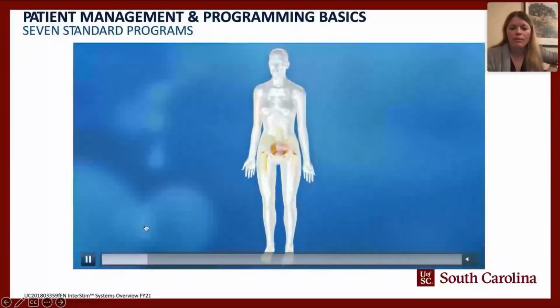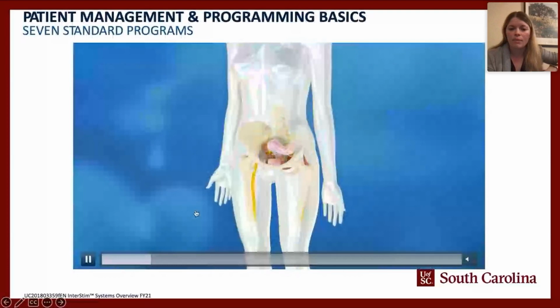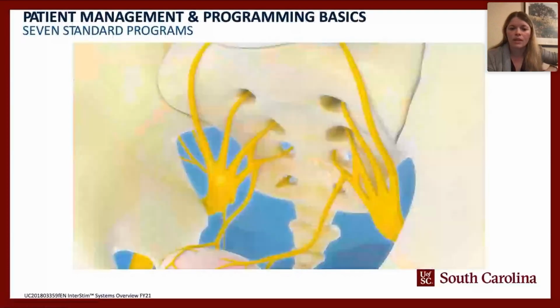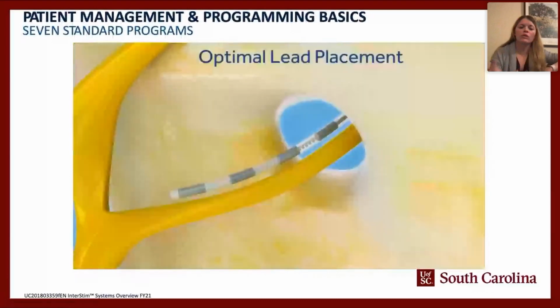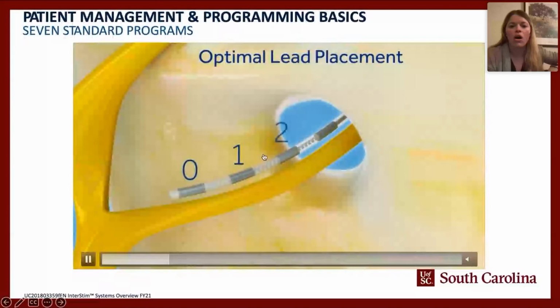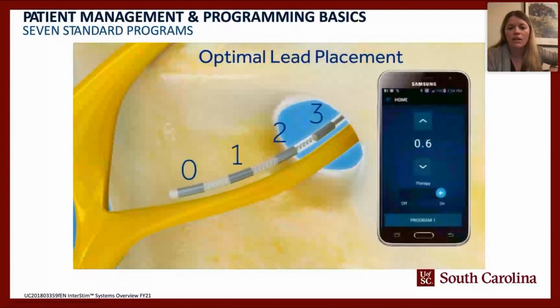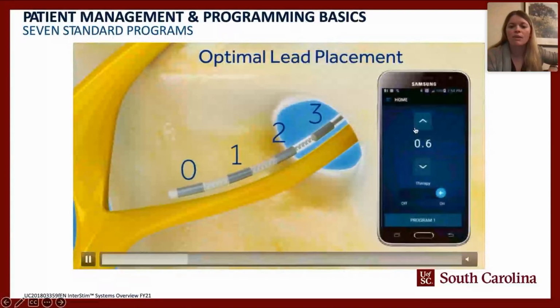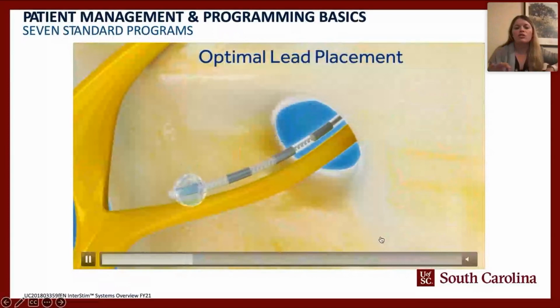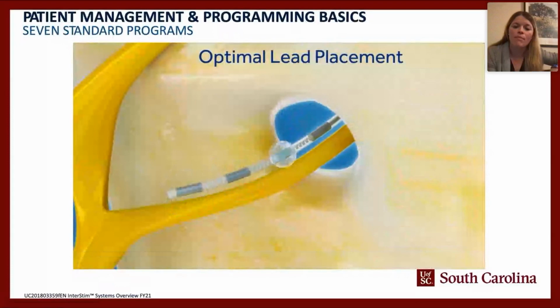So with the placement of the lead, that's going to be in the S3 nerve root, and the whole goal is to have that lead really follow the direction of the nerve. That's optimal lead placement, so that all 4 electrodes are adjacent to that nerve, and you're getting that inferior lateral direction to the lead. The goal is to have each of them stimulate the nerve in less than 2 milliamps; that is a good placement.